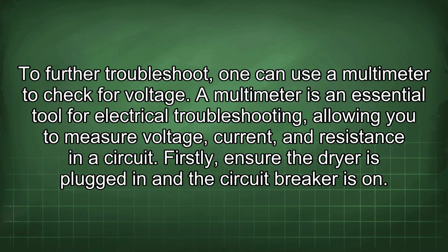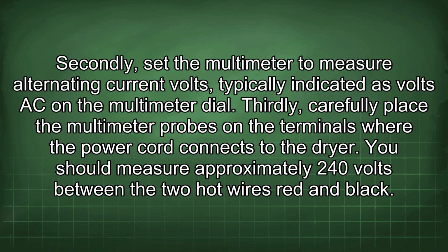To further troubleshoot, one can use a multimeter to check for voltage. A multimeter is an essential tool for electrical troubleshooting, allowing you to measure voltage, current, and resistance in a circuit. Firstly, ensure the dryer is plugged in and the circuit breaker is on. Secondly, set the multimeter to measure alternating current volts, typically indicated as volts AC on the multimeter dial. Thirdly, carefully place the multimeter probes on the terminals where the power cord connects to the dryer. You should measure approximately 240 volts between the 2 hot wires, red and black.